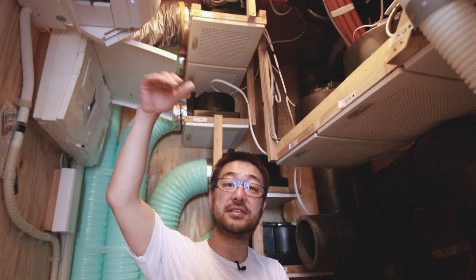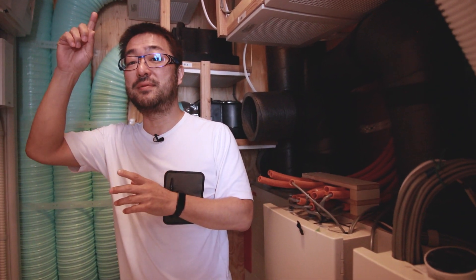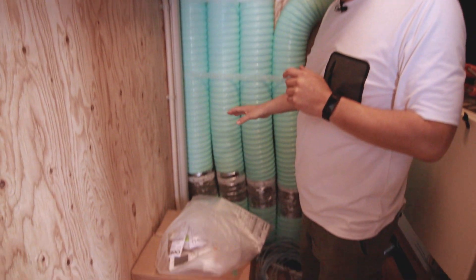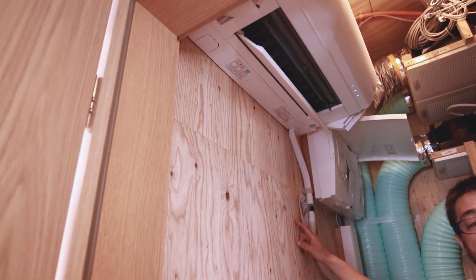This is the machine room. We have an electronic dust collector that filters all outdoor PM2.5. You can feel the cold fresh air coming in here from outside. That air is warmed by a single AC unit and distributed to every room via duct. The reason it's placed on the third floor is that we only designed it for summer cooling — winter heating is just supplementary because the south-facing solar gain alone can heat the house. The AC is 4kW — a 12-tatami unit — but it can serve 8 to 10 times that, so effectively about 120 tatami.